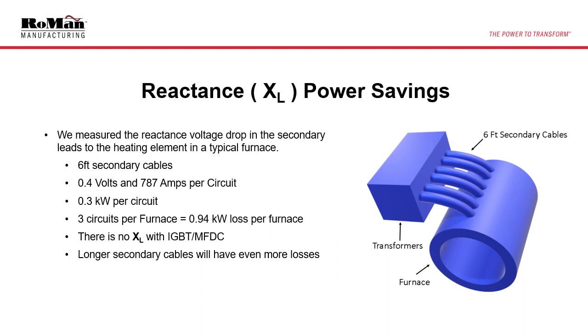We actually measured these losses in a furnace application. We measured the reactance voltage drop in the secondary cables of a 3-transformer furnace system. The length of cables from the transformer to the furnace was only 6 feet. By measuring AC and DC resistance, we determined that 0.4 volts were lost in each circuit due to reactance.